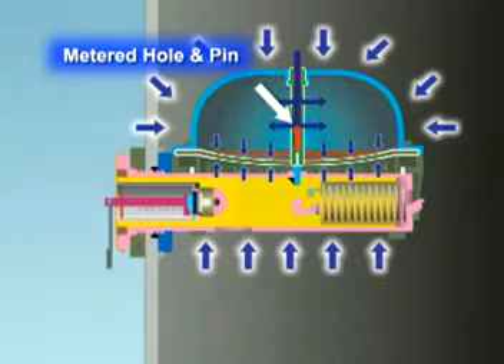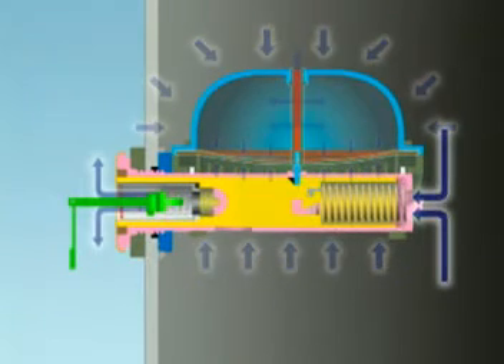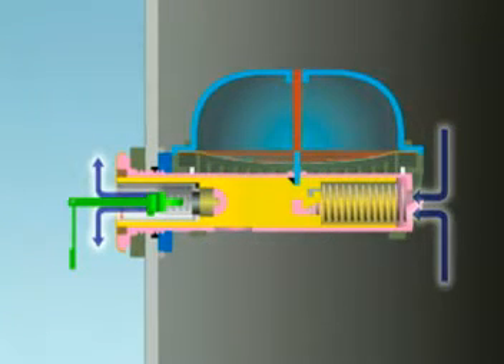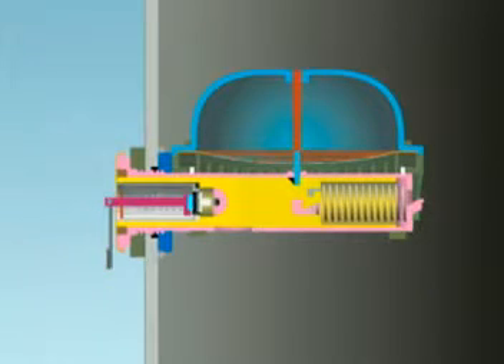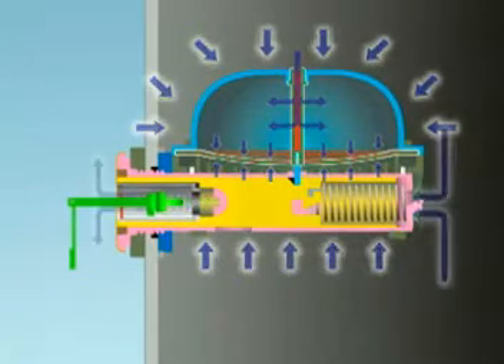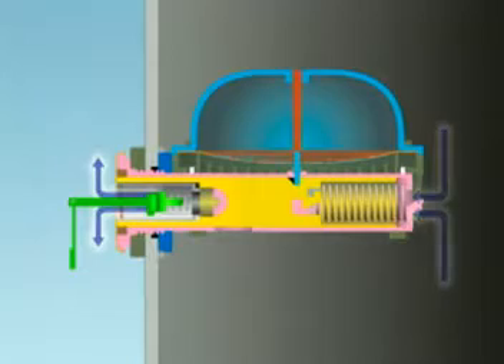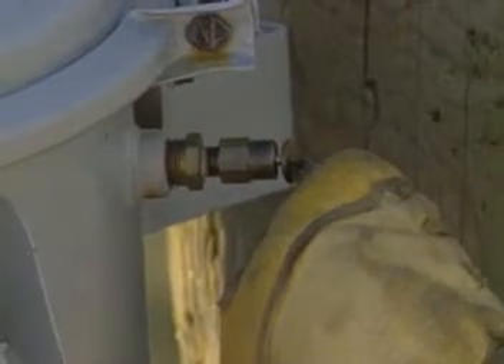Once the tank pressure builds up, the PRD opens, allowing air to escape. The PRD will close once the pressure is reduced. This operation will continue until the transformer cools down. Note that the IFD pressure relief device can be operated the same way as other transformer pressure relief valves.